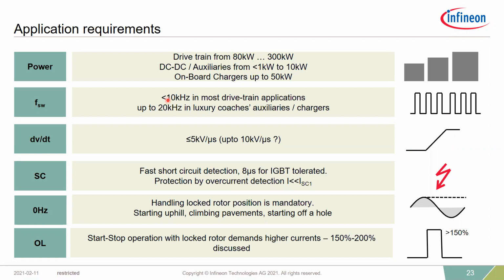But in general, the motor used to be switched at a low frequency, because this limitation is coming from the dV/dt. This is the standards limitation. Mainly the motor cable has a limitation of less than 5 kV per microsecond.